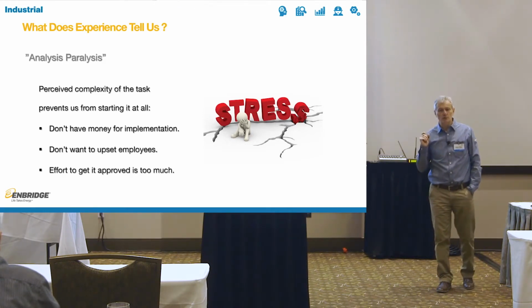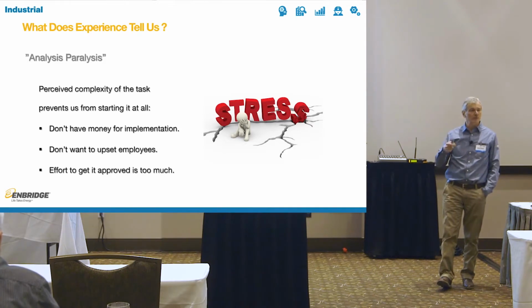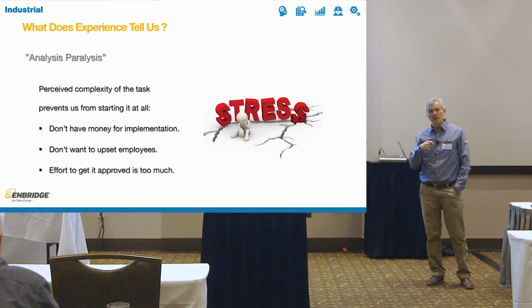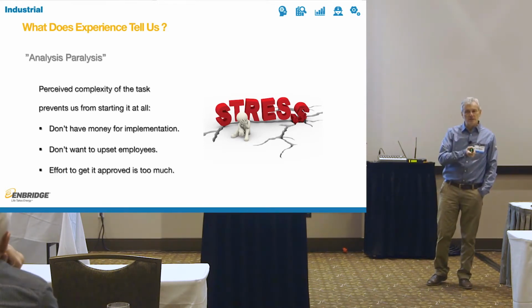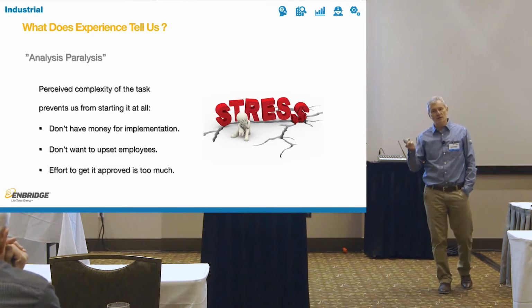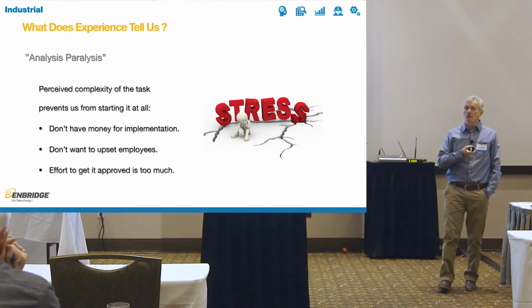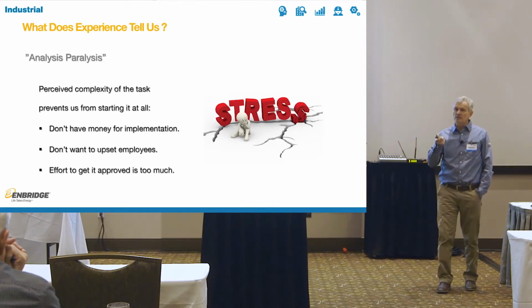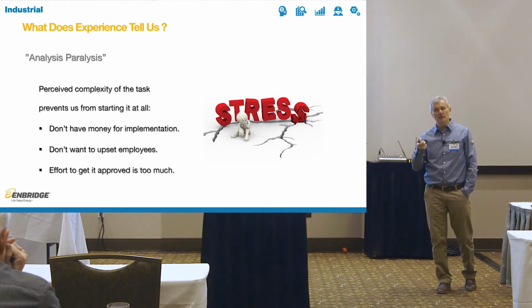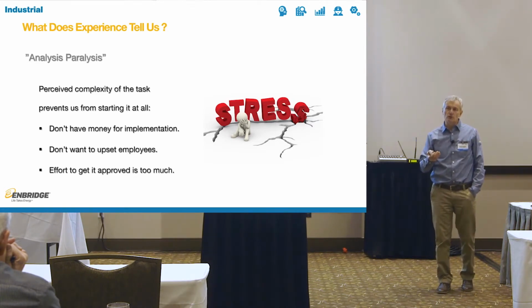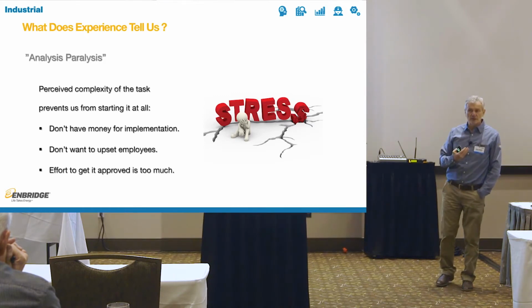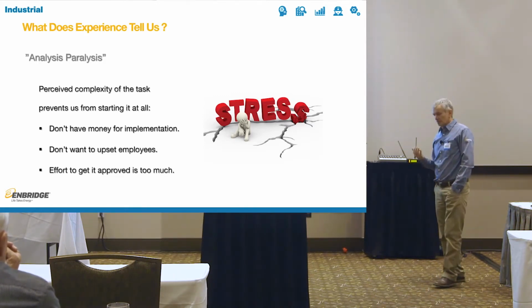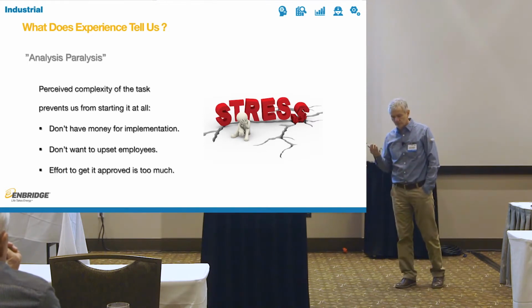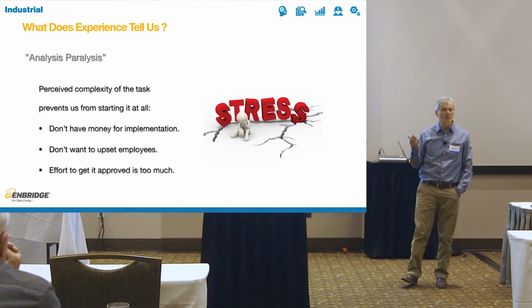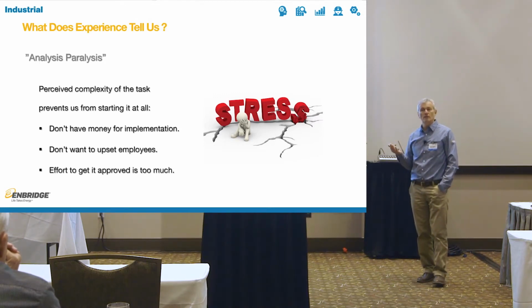We actually implemented one of those exhaust reductions in the facility systems where we saved 1 megawatt of electricity in a unionized facility by working with the union, indoor air quality technicians, and their maintenance, and we convinced them that the actual quality of air improved once we reduced the exhaust. But it required that maintenance manager who worked with me to be really patient and explain the process to the union, get them in, and we got everybody agreed that this is the right way to do it. They saved something on the order of 400,000 cubic meters in gas, 1 megawatt in electricity by doing that project.